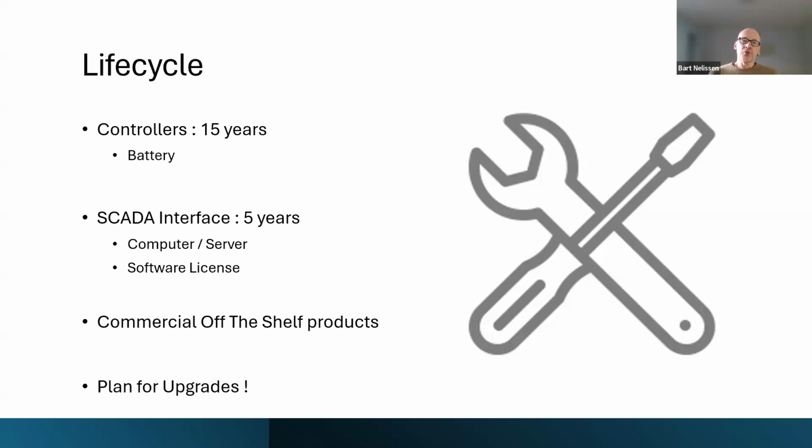My point is that if you don't plan for that 15 years, then 15 years from now, you are going to be looking at major cost and a massive impact to your operation to upgrade those controllers. And that's currently what we're doing. In our industry, we've noticed that a lot of our users, a lot of our municipalities haven't planned for these upgrades. And when the controllers start failing or they are no longer supported by vendors, it becomes a big challenge to maintain your critical infrastructure on those controllers. So plan for about 15 years.